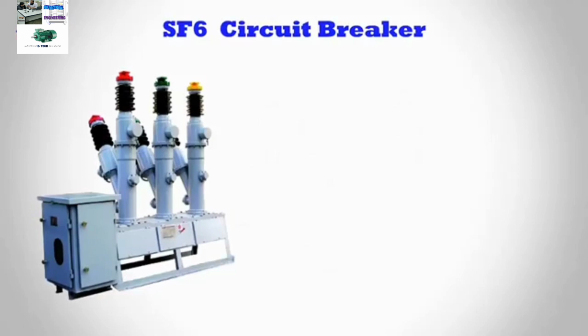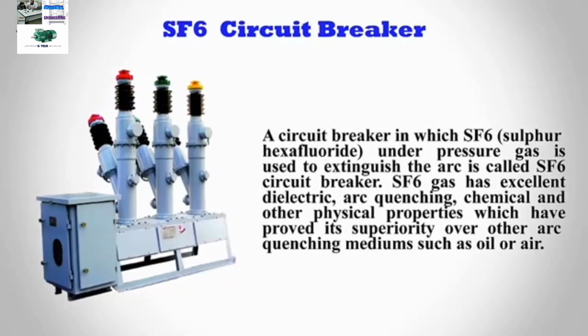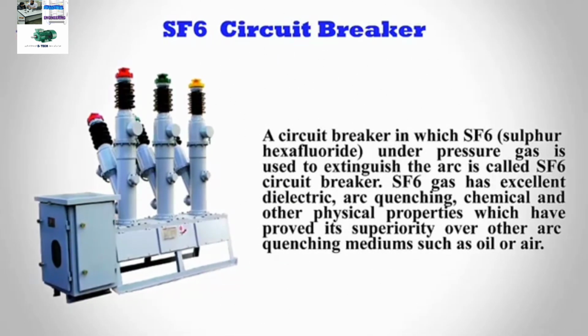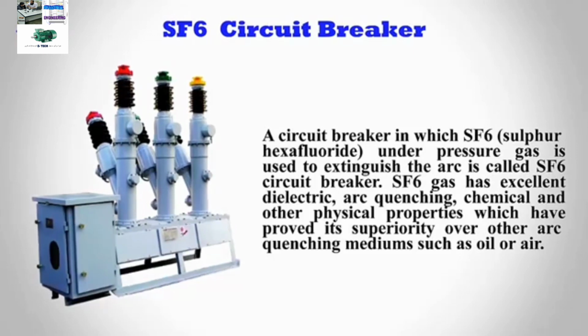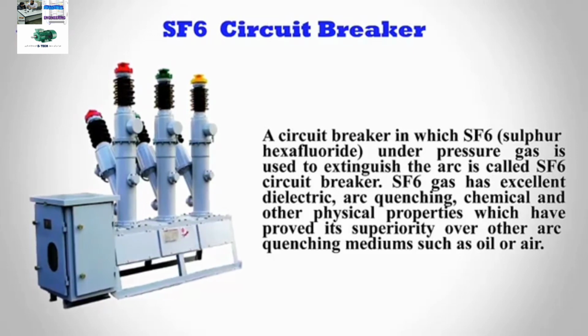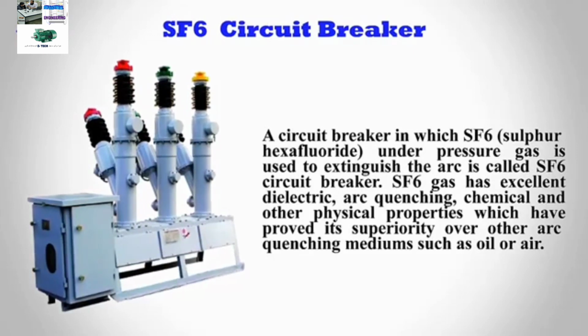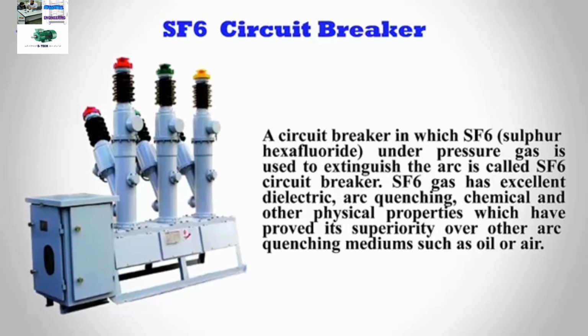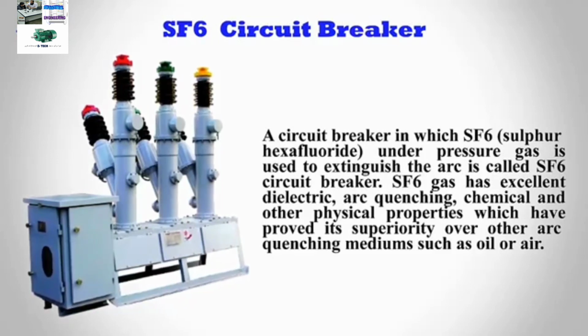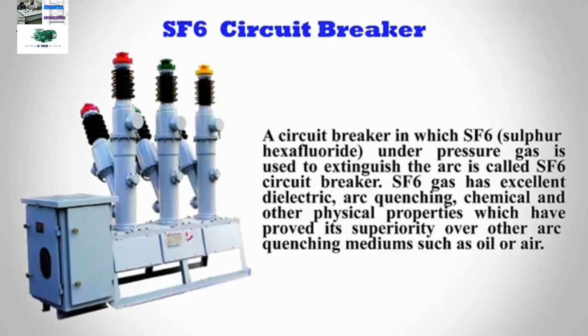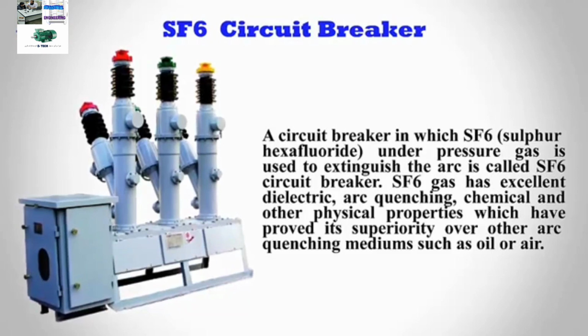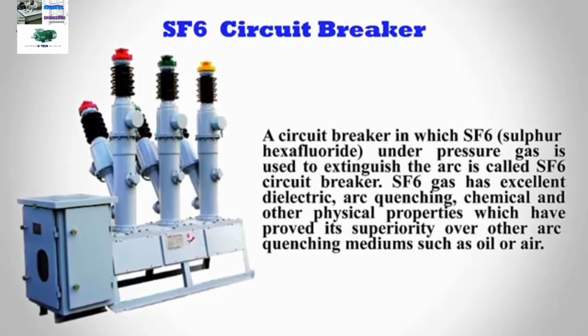A circuit breaker in which SF6 gas under pressure is used to extinguish the arc is called an SF6 circuit breaker. SF6 gas has excellent dielectric, arc quenching, chemical and other physical properties which have proved its superiority over other arc quenching mediums such as oil or air.